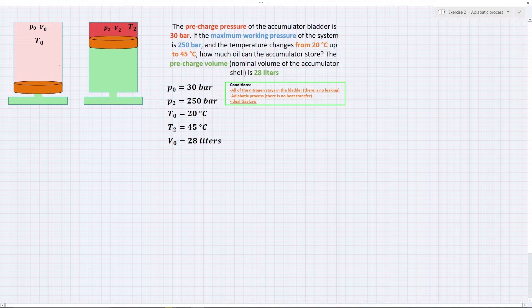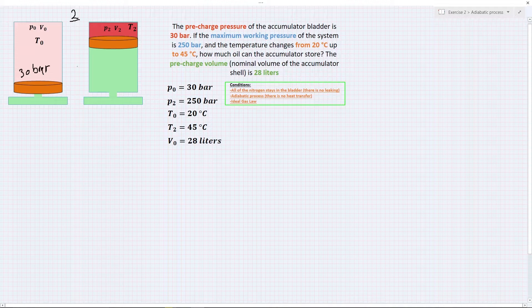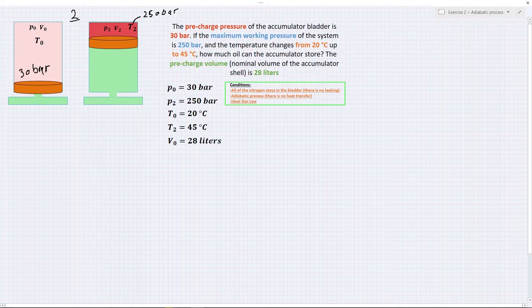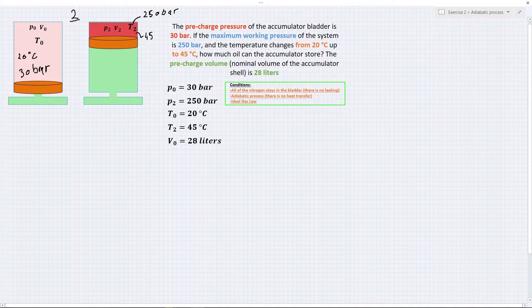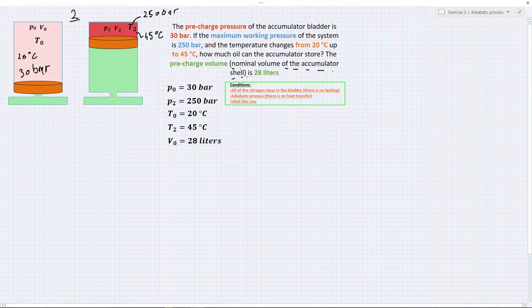Let's look at example two. The pre-charge pressure of the accumulator bladder is 30 bars. The maximum working pressure of the system is 250 bars. The temperature changes from 20 degrees Celsius up to 45 degrees Celsius. How much oil can the accumulator store? The pre-charge volume, or nominal volume of the accumulator shell, is the volume of the whole accumulator when the bladder fills the shell completely.